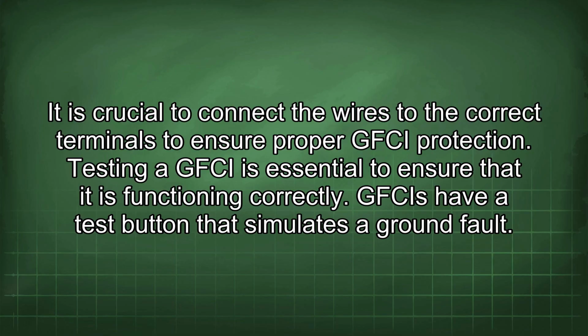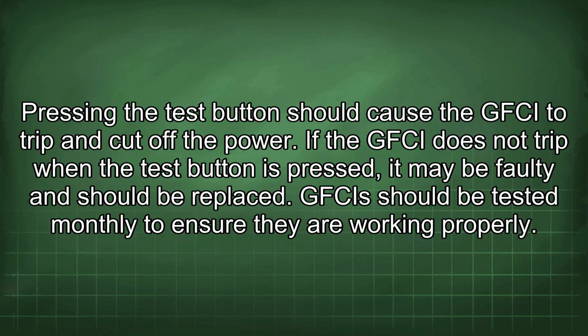Testing a GFCI is essential to ensure that it is functioning correctly. GFCIs have a test button that simulates a ground fault. Pressing the test button should cause the GFCI to trip and cut off the power. If the GFCI does not trip when the test button is pressed, it may be faulty and should be replaced. GFCIs should be tested monthly to ensure they are working properly.